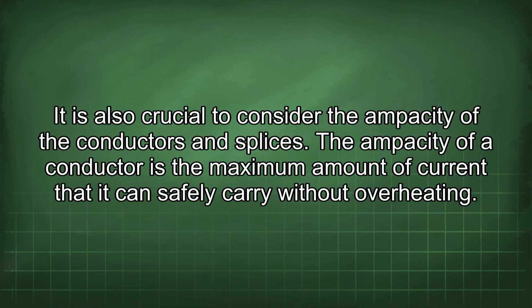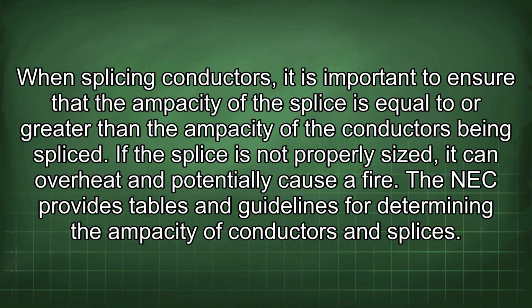It is also crucial to consider the ampacity of the conductors and splices. The ampacity of a conductor is the maximum amount of current that it can safely carry without overheating. When splicing conductors, it is important to ensure that the ampacity of the splice is equal to or greater than the ampacity of the conductors being spliced. If the splice is not properly sized, it can overheat and potentially cause a fire.